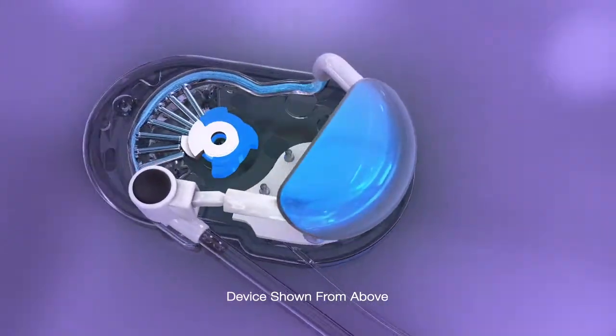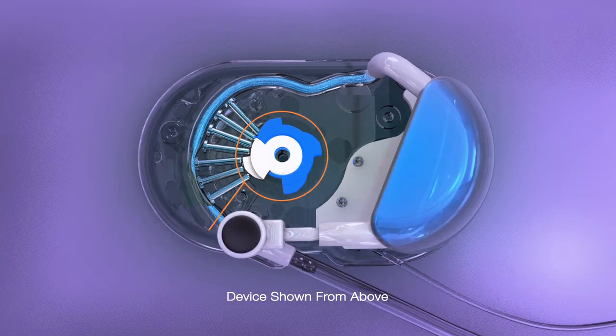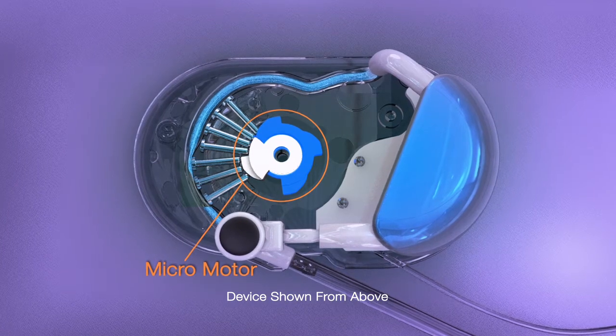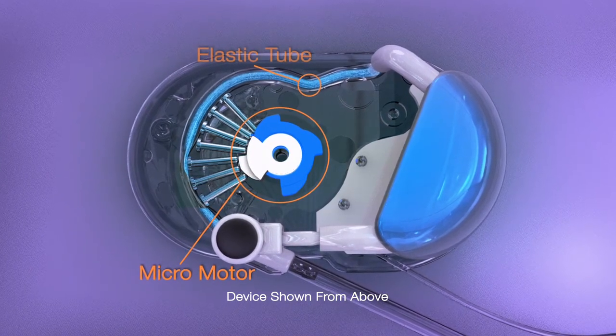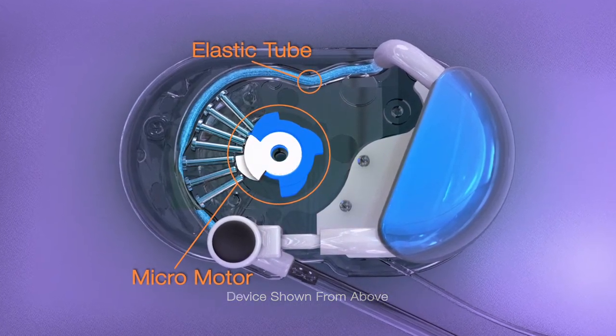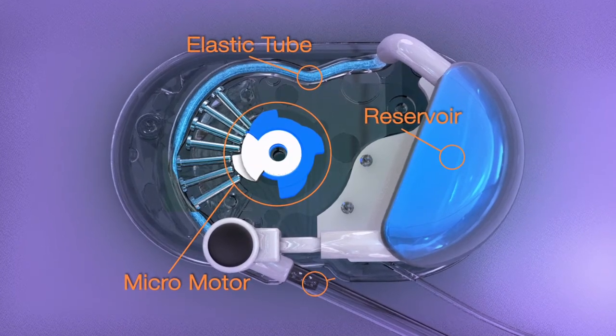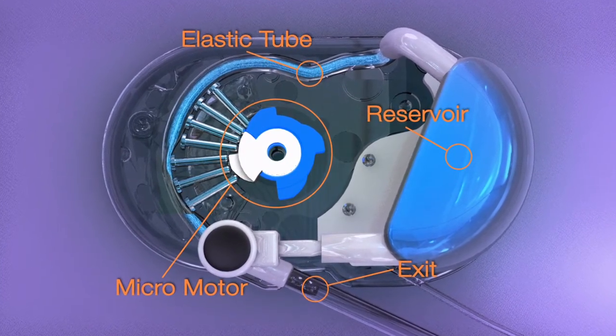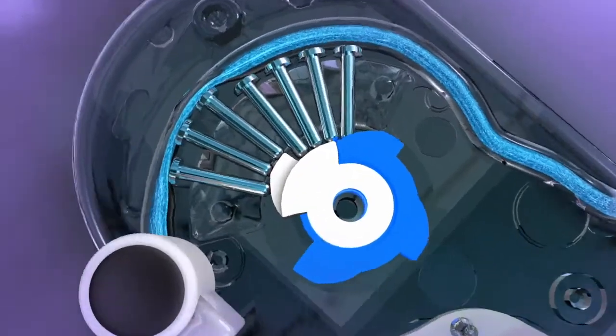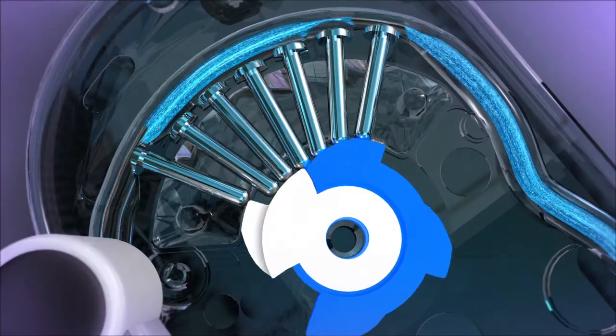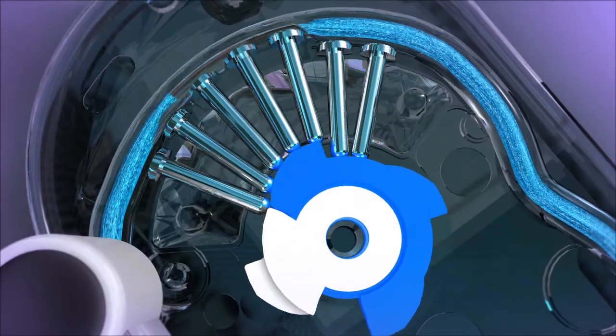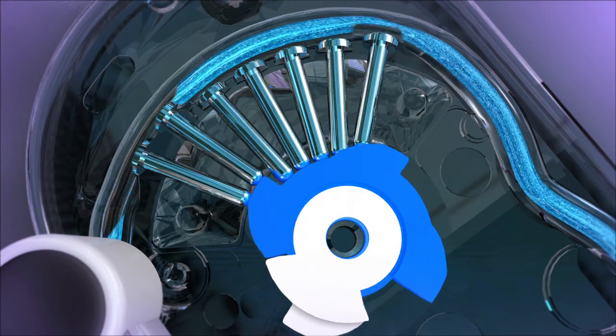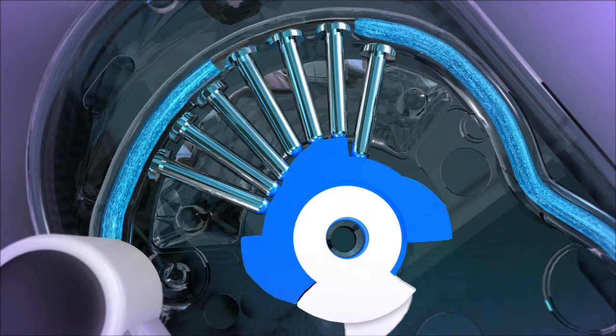iPrecio is equipped with a very small battery-operated micromotor which rotates anti-clockwise at a very slow speed. An elastic tube that contains the infusion solution extends from the reservoir to the exit point of the pump. The shaft of the pump motor is equipped with a rotating cam.